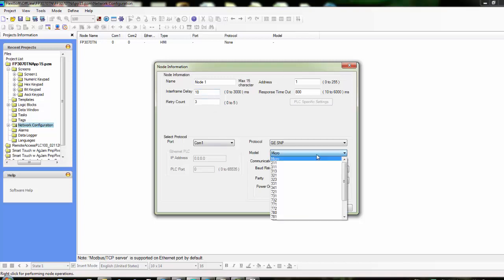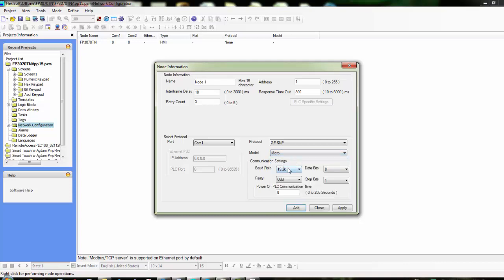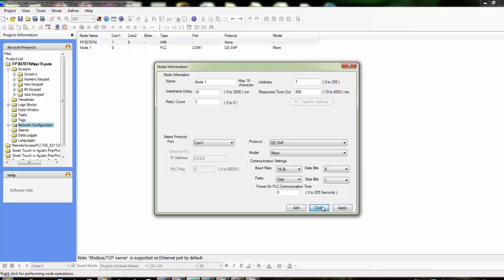We could choose which model of the SNP PLC that we're choosing. For this we'll just choose a Micro, and then we can define our baud rate settings and parity, data bits, stop bits. We can also choose the time delay for the PLC communication, so it'll wait for the PLC to come up before it starts to try to communicate. So now we'll click Add. That basically adds this node—a GE SNP Micro PLC.